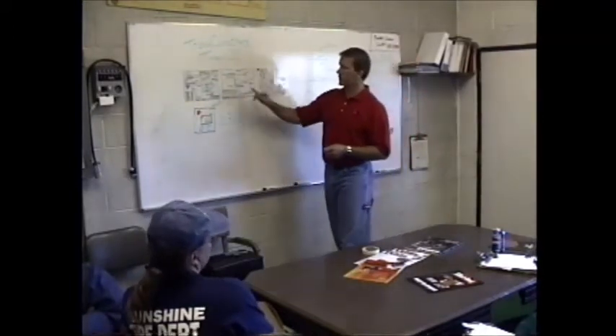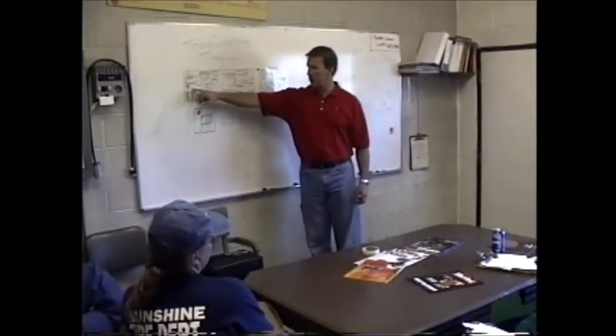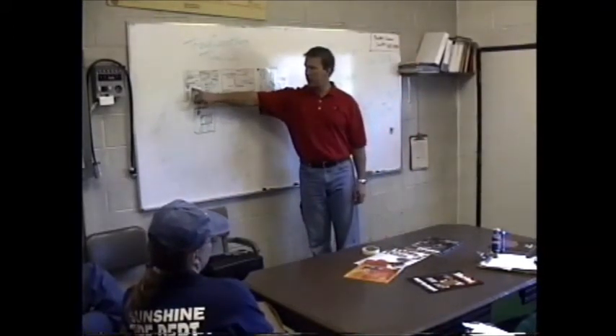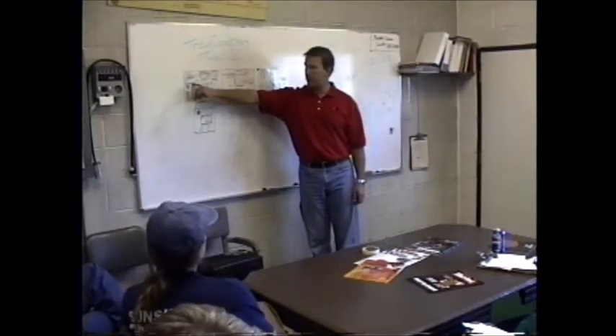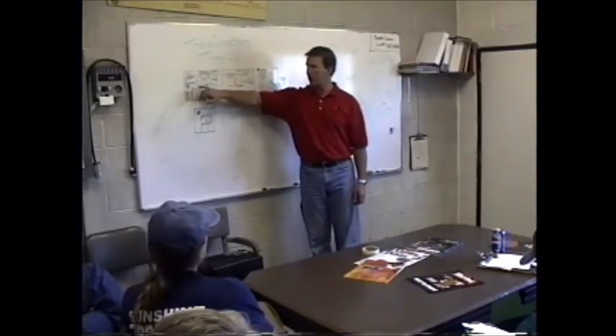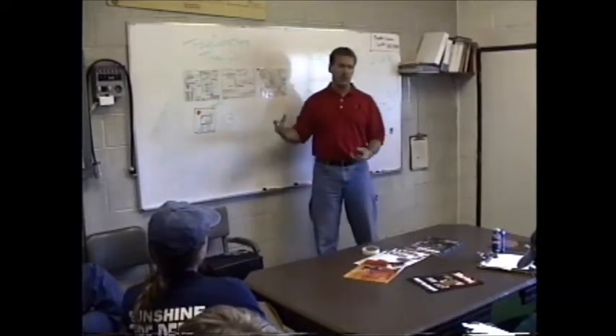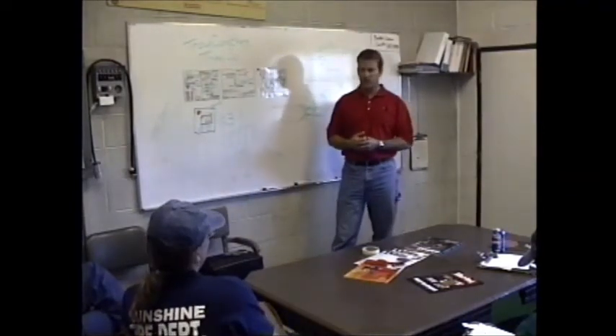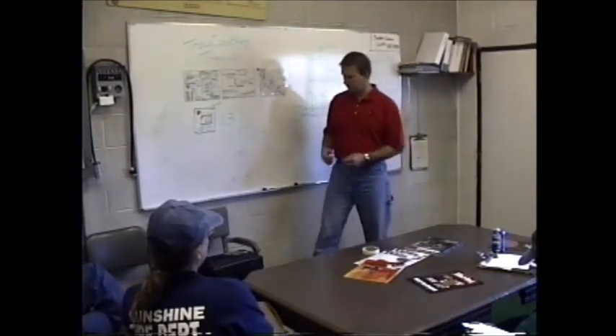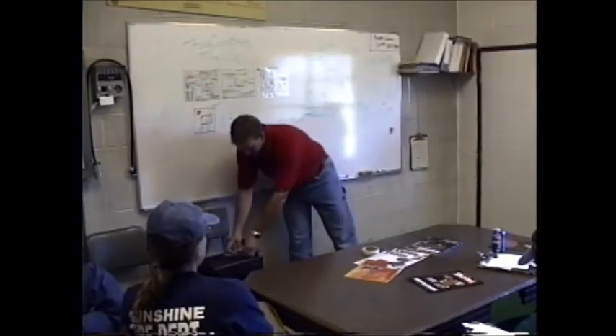That pretty much covers it on these 2 schematics, other than there's an automatic pressure control valve here that gets a water pressure signal from that pump, that foam line, as well as a pressure gauge that would tell you exactly what the pump pressure is in that line. But what I'll hit on here next is your air compressor.